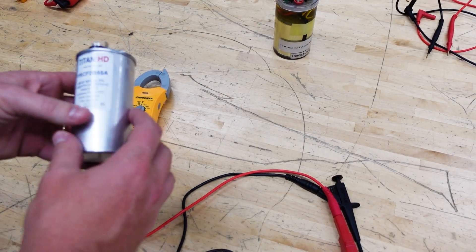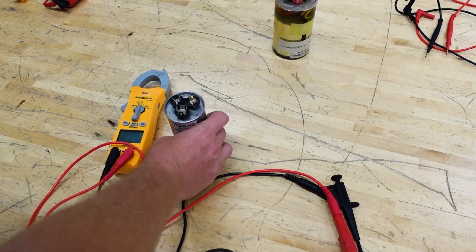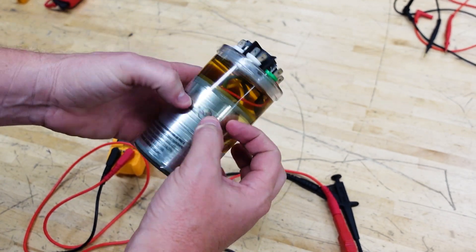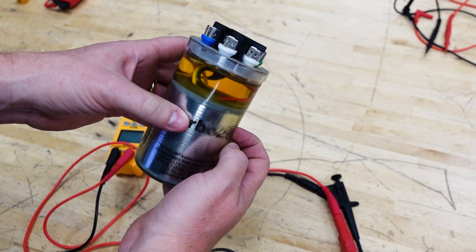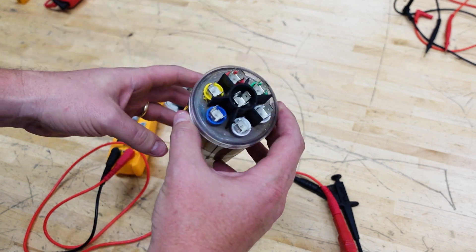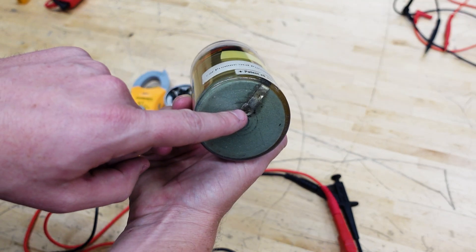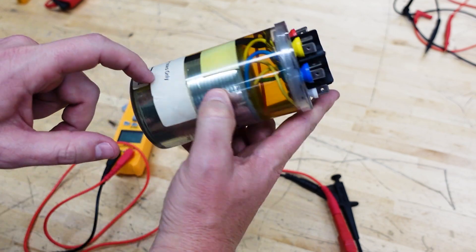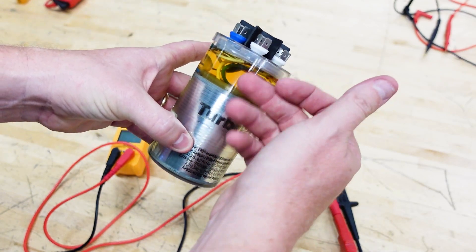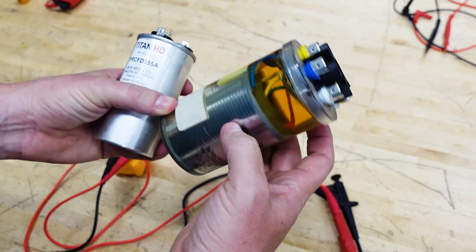One of my favorite topics is run capacitors because they're so often misunderstood. Inside these things we basically have wraps of plastic with a metallic coating on either side, an oil fill, and connections. This is a dual run capacitor so it has a lot more wires and connections inside it than a normal capacitor. Your common or C terminal connects to one side — the bottom — which goes up to a ribbon connecting to the center, and the other side of the foil connects to your other capacitors, as is typical with a dual cap.